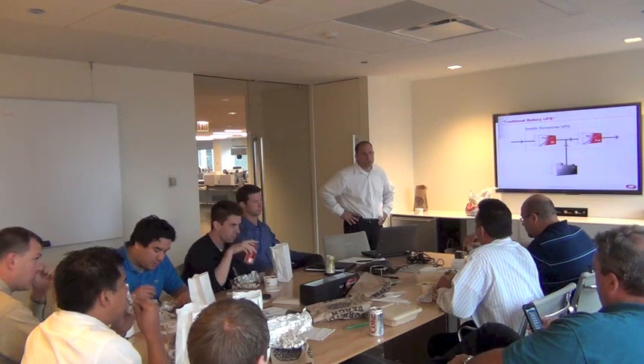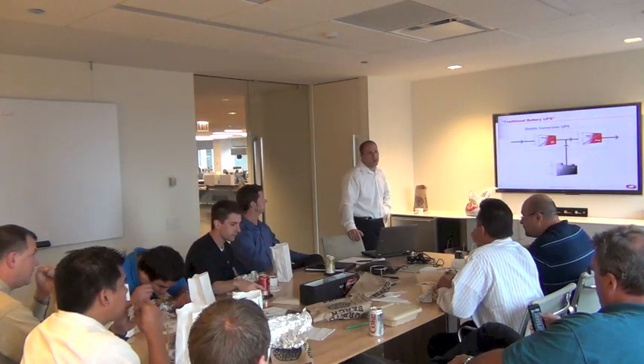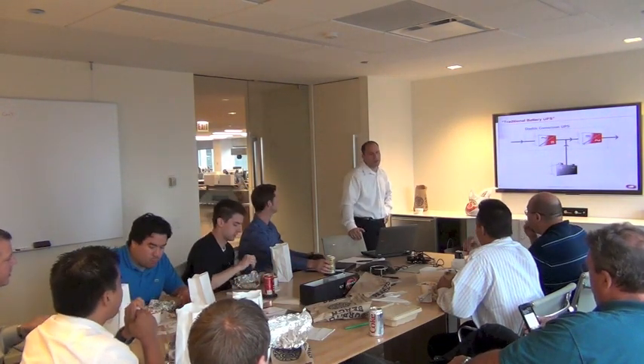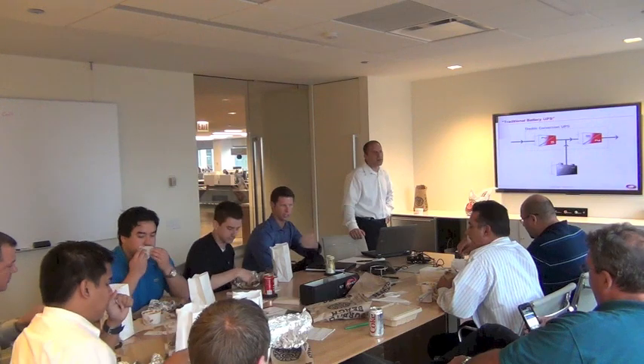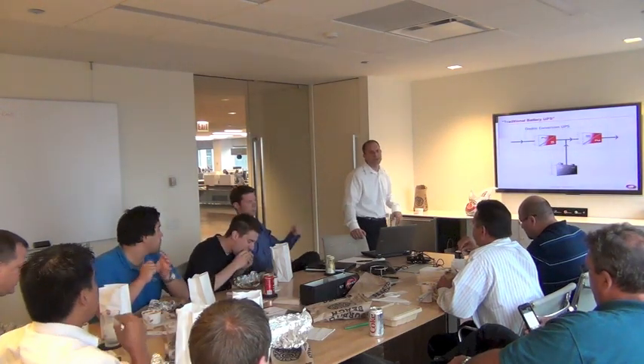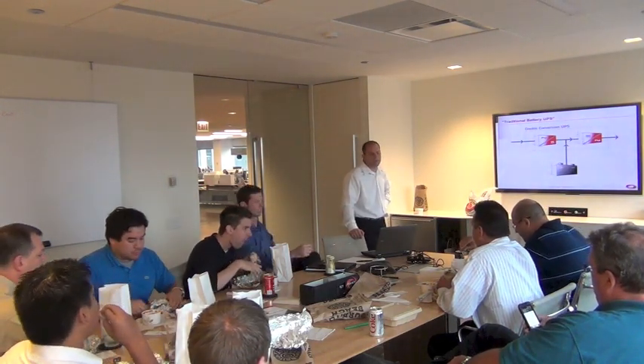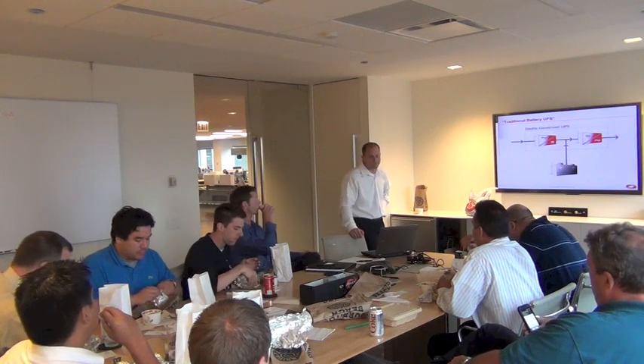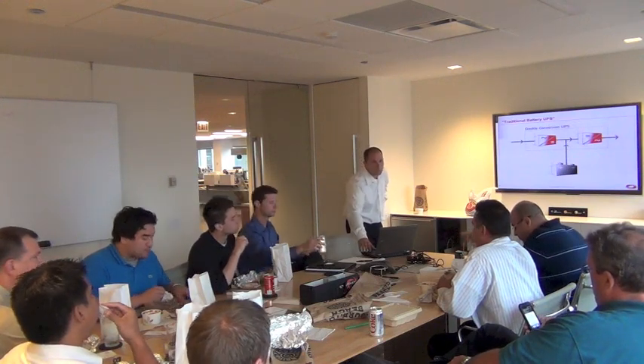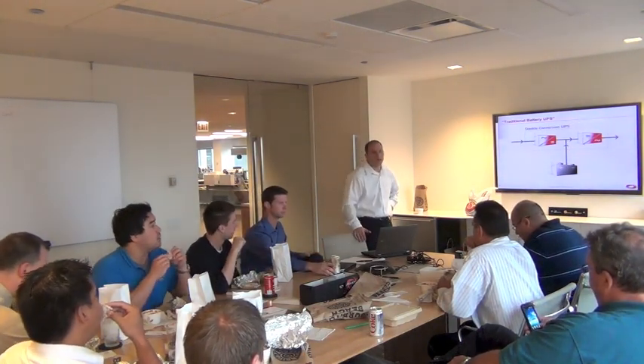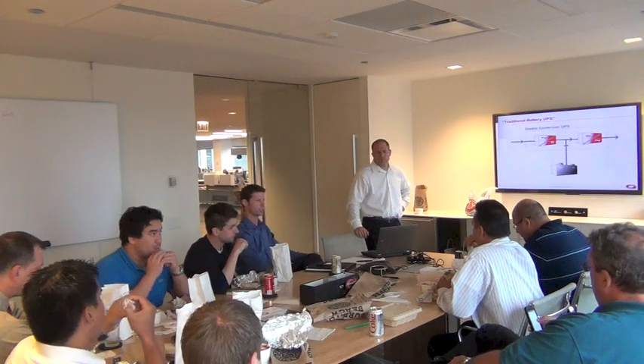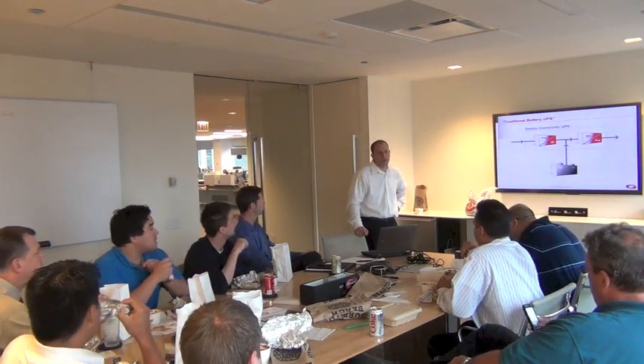Was that 99%? On some of the new boxes, they have eco mode. Yeah, in eco mode, because they're not conditioning the power, they're just putting it in bypass, basically. Yeah, right. It's in bypass, but then instantaneously goes to UPS. And they do publish a short transfer window, a full cycle, and it's within the CBEMA curve.